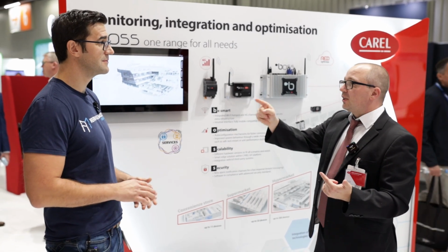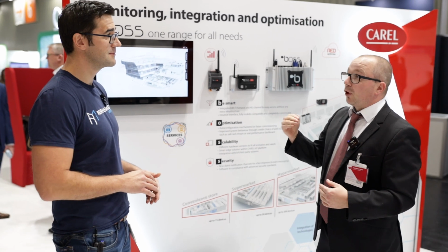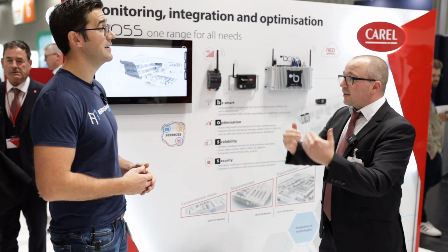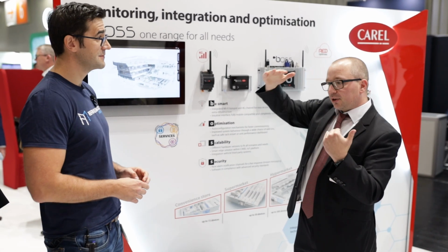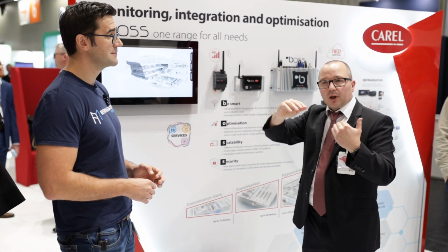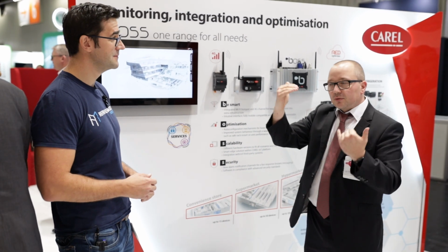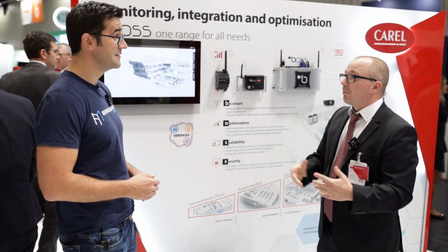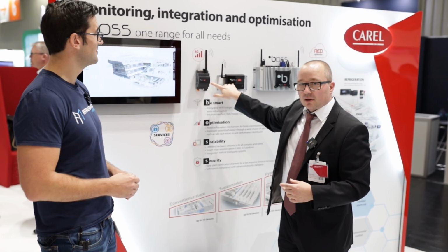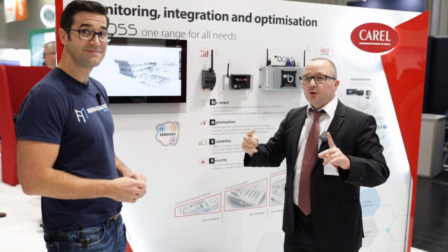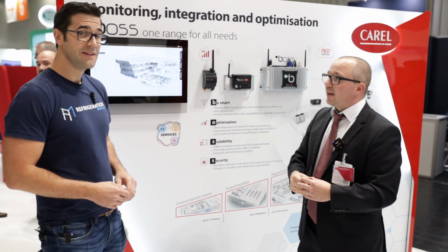Supervisory. Here we are talking about floating suction, floating condensing. These are the things to shift our suction pressure a little bit higher and to lower our condensing pressure to have the best energy efficiency possible. This is done with controllers like this, or with the monitoring system like this, and controllers like the MPX. They are able to do this.